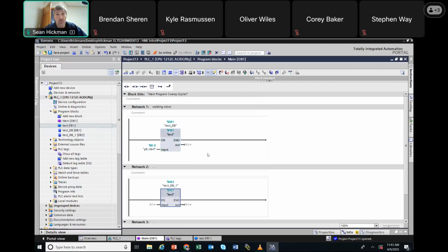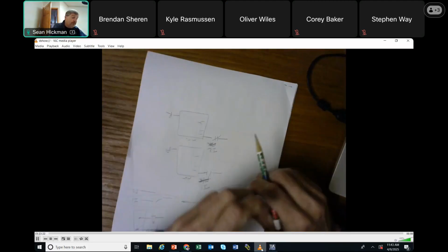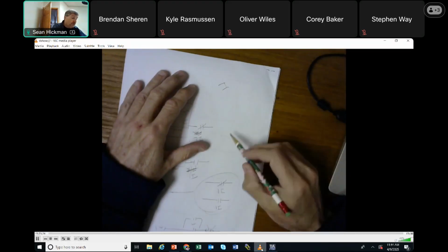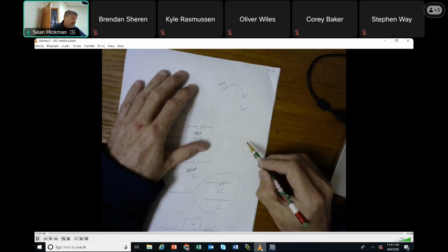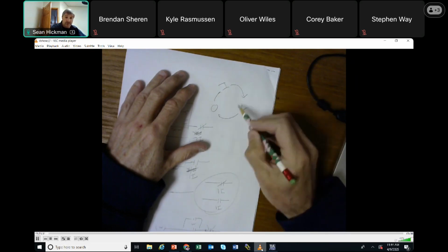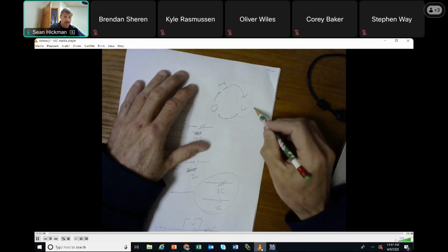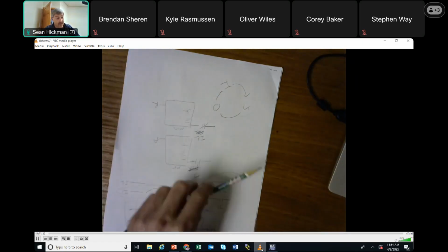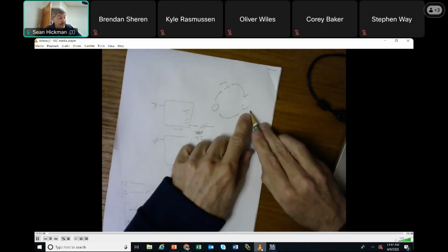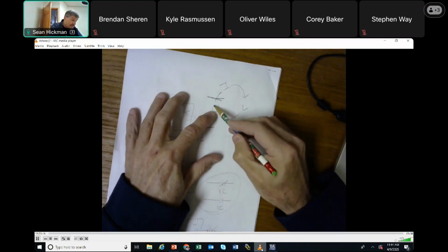It will. And so what we've got going, and the difference of these controllers, especially because of the scheduling issues, on the Allen Bradley, we learned that you check the inputs, you solve the ladder logic, and then you update the outputs, and then you start again, keep running around just like that. Inputs, ladder, outputs, inputs, ladder, outputs. And the timers and everything are in the ladder logic. And everything would be updated right here at the outputs, and then it would start again.